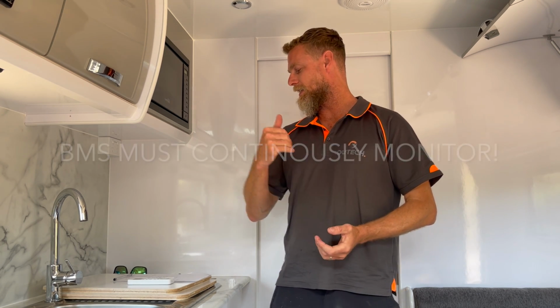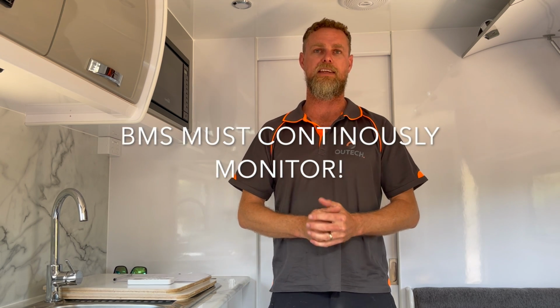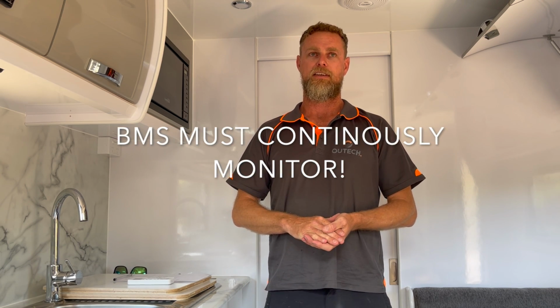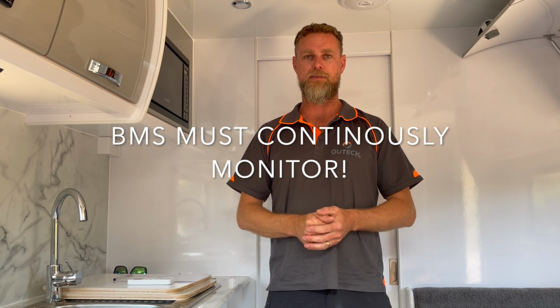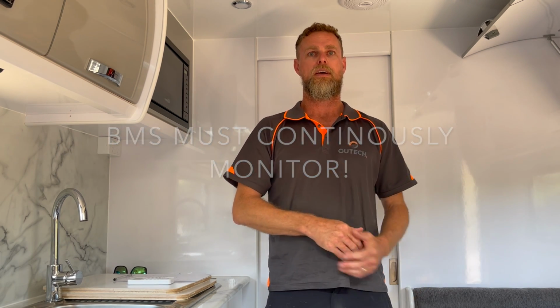The second thing is the BMS needs to continuously monitor. Continuously means permanently connected, not switched off, not able to be turned off. It needs to monitor over voltage and under voltage, over temperature and under temperature, and over current. So those five things need to be monitored by the BMS.